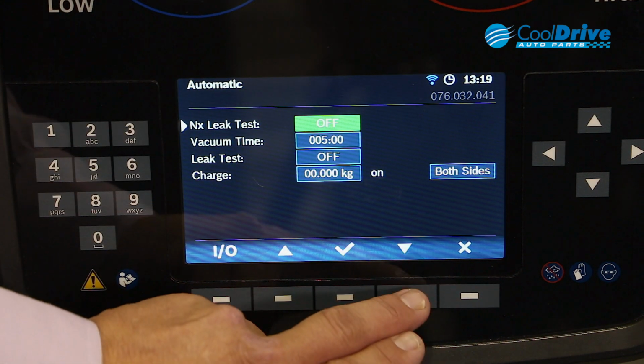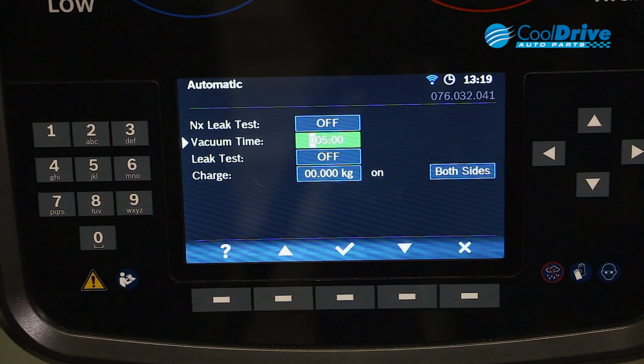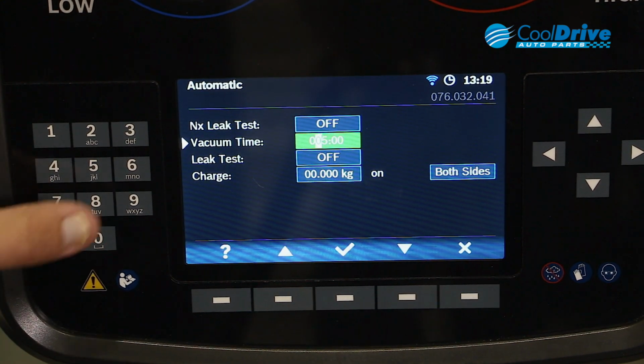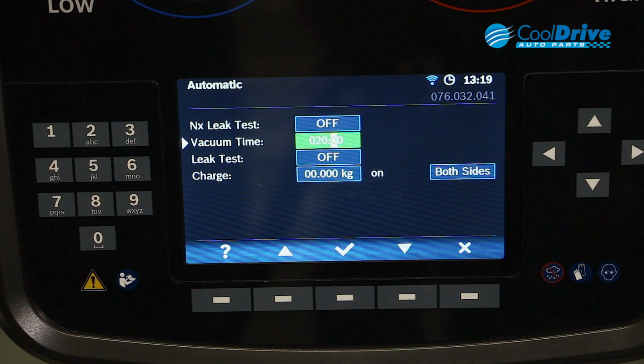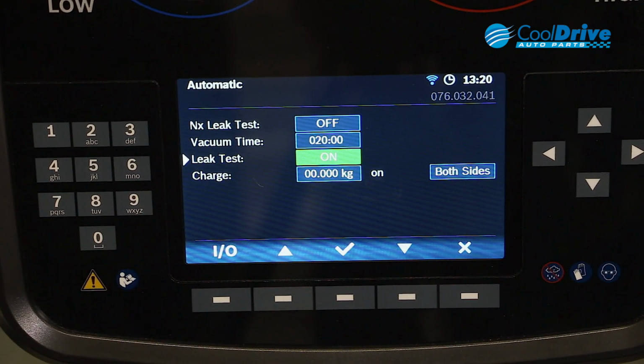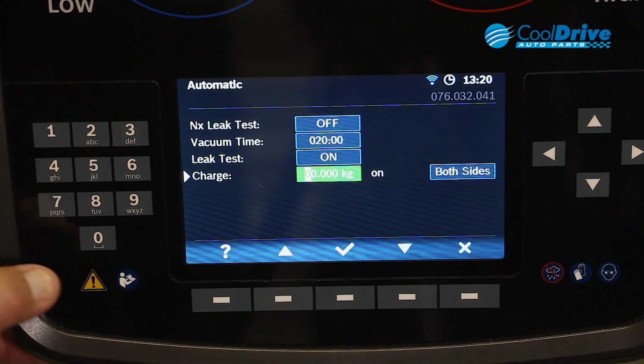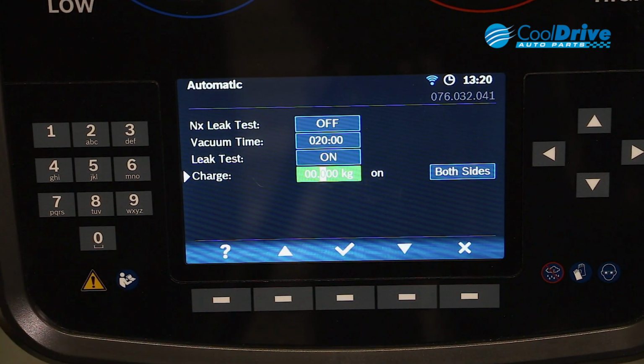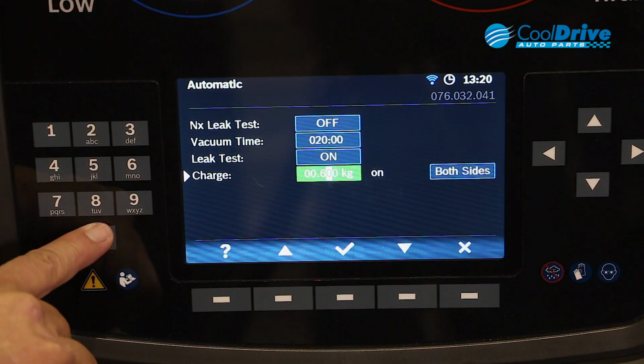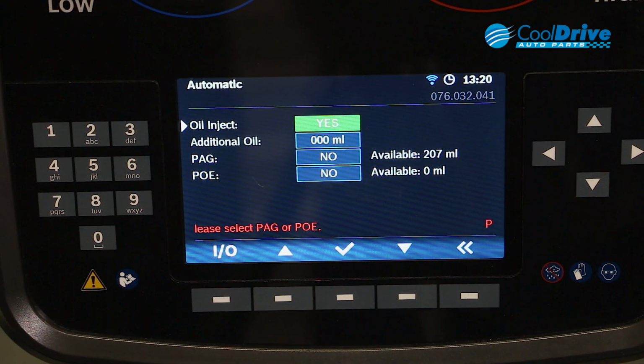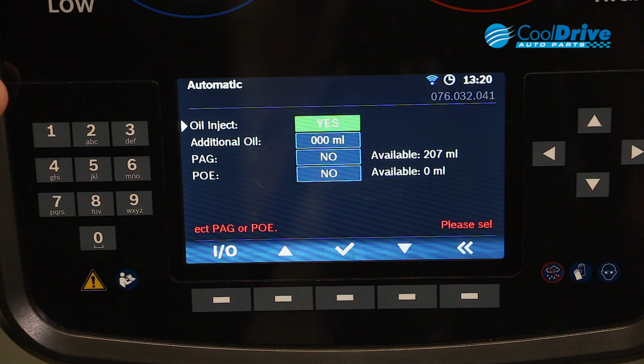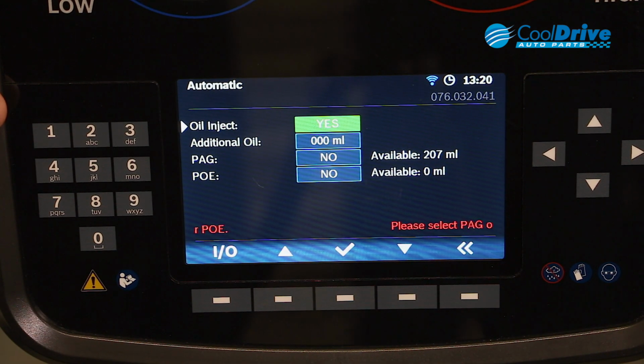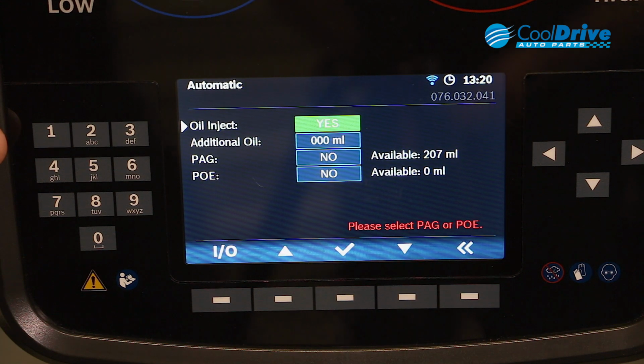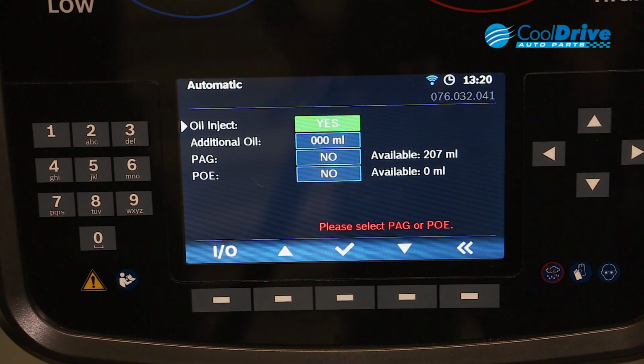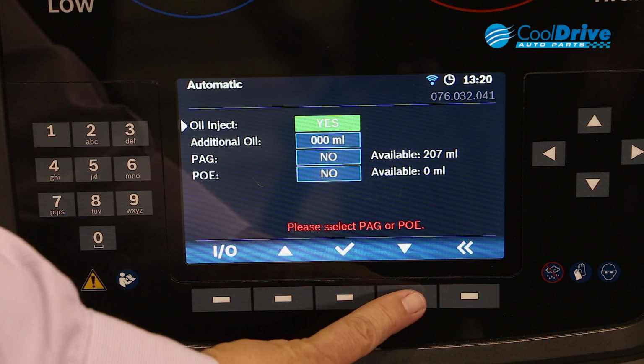So nitrogen leak test we actually aren't running. We'll set our vacuum time through to 20 minutes. We'll actually perform a leak test and we'll set our charge to 600 grams. From here we have the options of oil inject, yes or no, additional oil, and select our PAG and POE. So we're actually going through and selecting our oil menu.